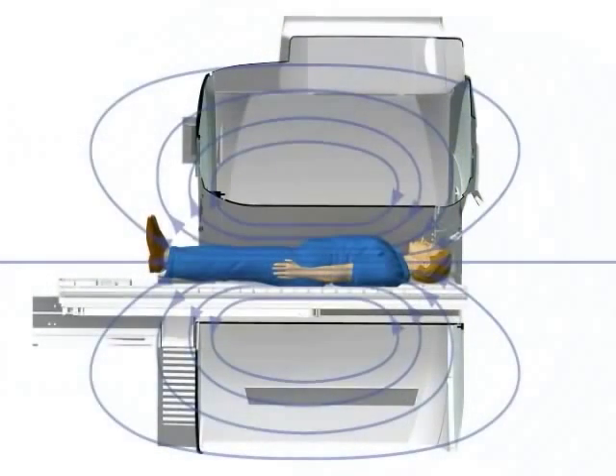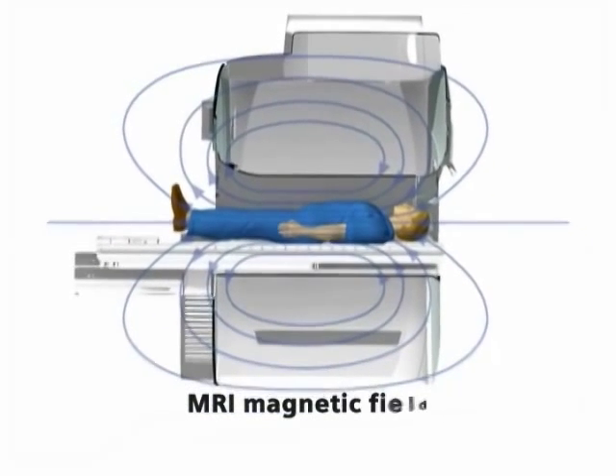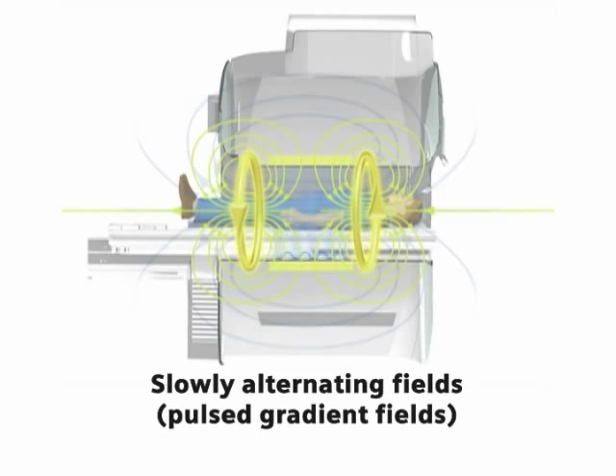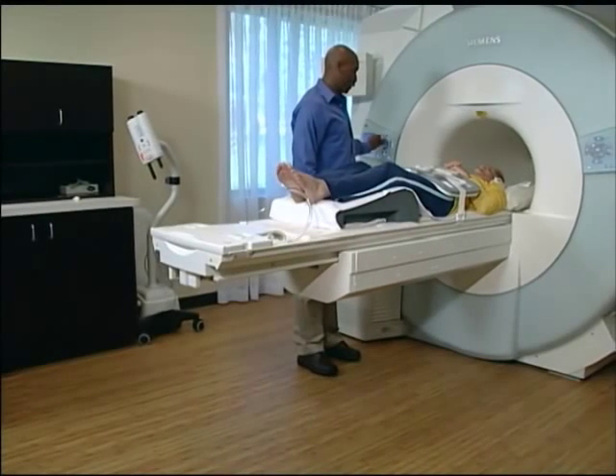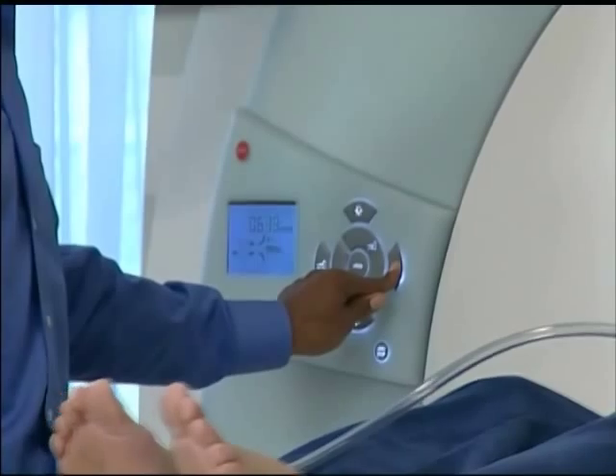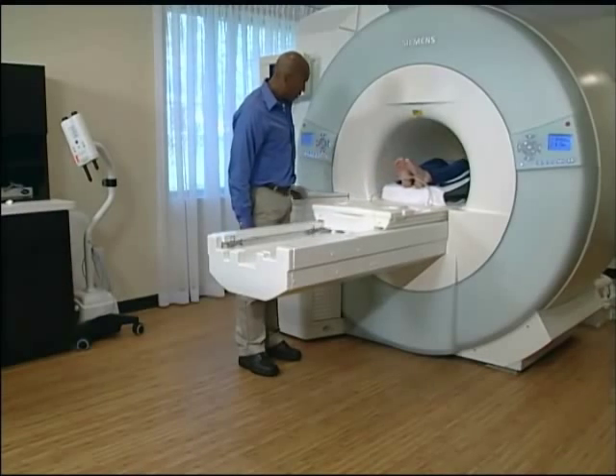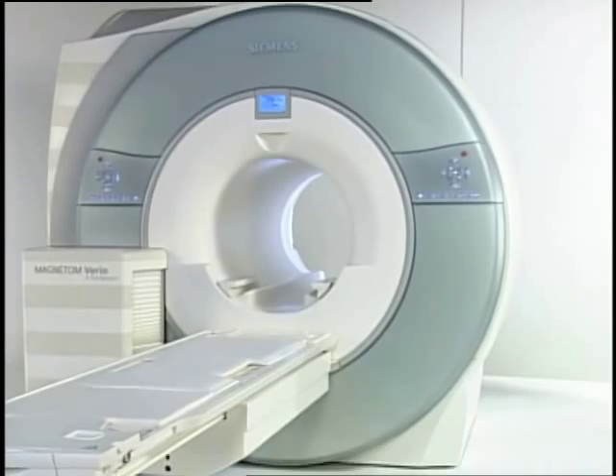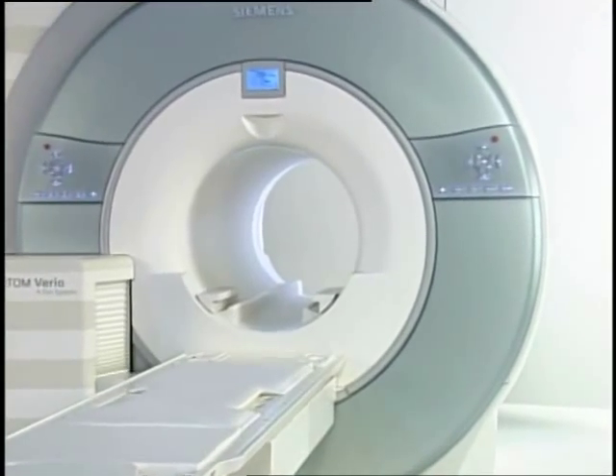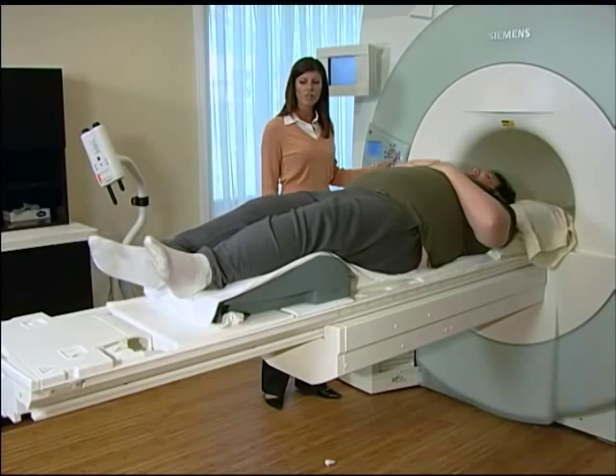Therefore, the patient is exposed to three different magnetic fields during the MR examination: the static main magnetic field that aligns the protons, the high frequency alternating fields that disrupt the alignment, and the pulse gradient field that enables correlation of the MR signals to the location of origin. All three fields affect the patient differently. The static magnetic field used in MR does not cause any lasting side effects. The same is true for alternating fields when used properly. The rapidly switched magnetic field gradients in combination with the static main magnetic field are the cause of the considerable noise created during an MR examination.